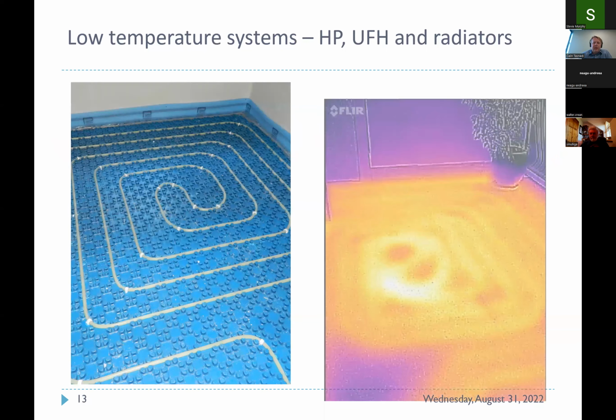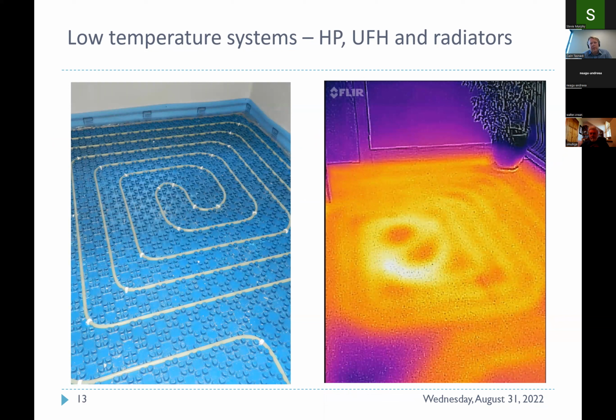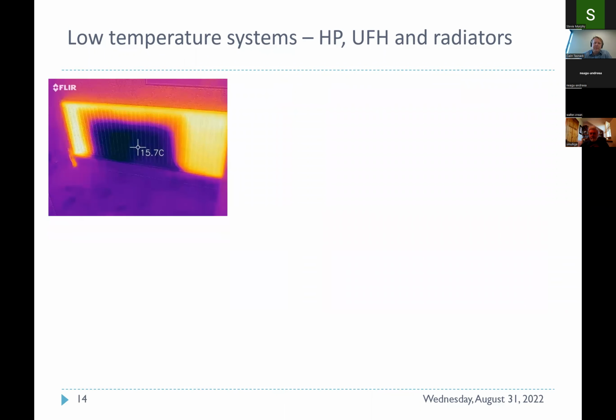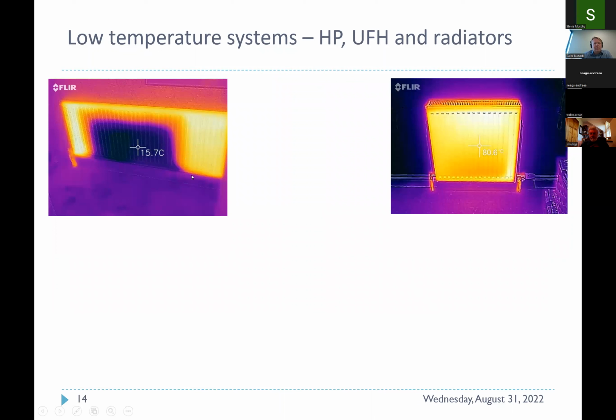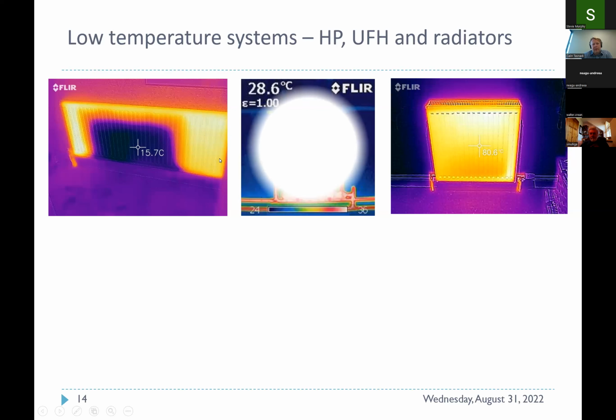Just another couple of examples now to show how the heat looks in an underfloor heating system. Very nice and very uniformly distributed. And then to show how a radiator that has been in use for a while, for example, and hasn't been cleaned, you can have cold spots on it. Then if you purge and clean, this is most relevant for retrofit applications, where people are thinking of reutilizing existing radiators. They all have to be properly double, triple flushed to make sure that any sludge in them has been cleaned, because this will impact greatly on the heat output of that radiator.